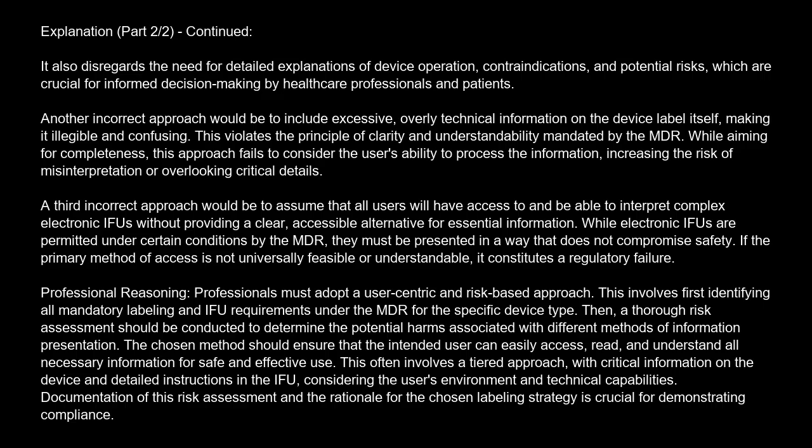A third incorrect approach would be to assume that all users will have access to and be able to interpret complex electronic IFUs without providing a clear, accessible alternative for essential information. While electronic IFUs are permitted under certain conditions by the MDR, they must be presented in a way that does not compromise safety. If the primary method of access is not universally feasible or understandable, it constitutes a regulatory failure.